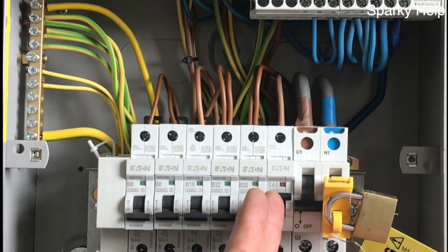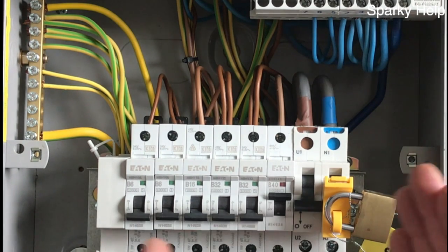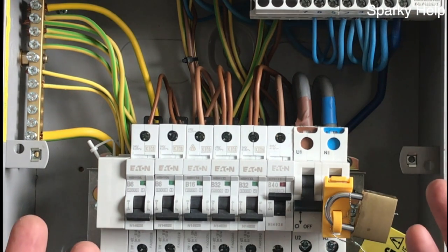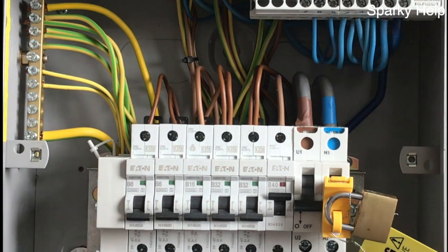All we need to know now is find out where it is, so we could break this circuit down, split the circuit. There's only be a few points on the shower circuit, the isolator, the shower itself. So test each section of that circuit and see which part of the circuit is at fault, and then replace it.